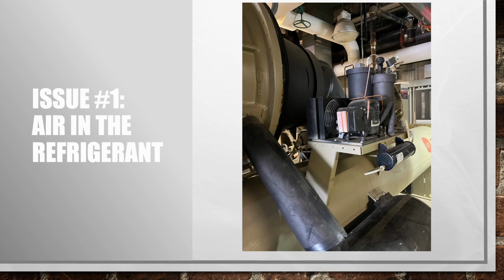Issue number 1. Air in the refrigerant. On these machines specifically, they're running in a vacuum, so it's really likely that you're going to get air that accumulates in the system over time, just operating. And if the thing's sitting for a long time, you're also going to get air accumulation in the system.